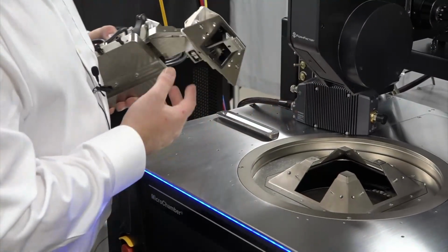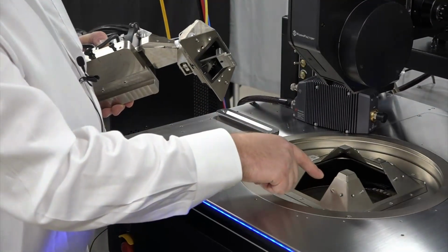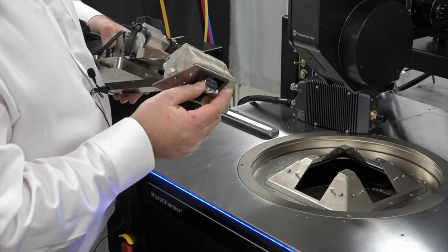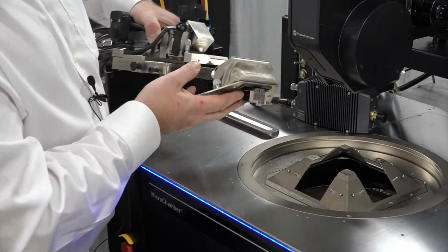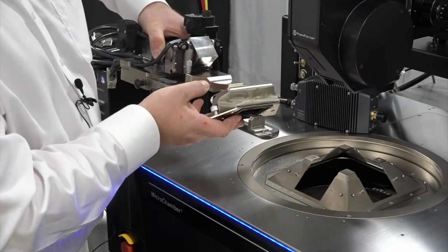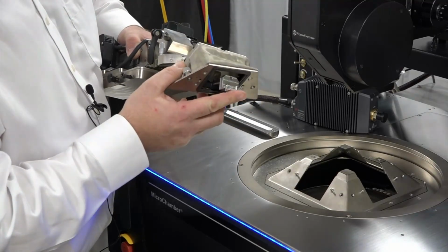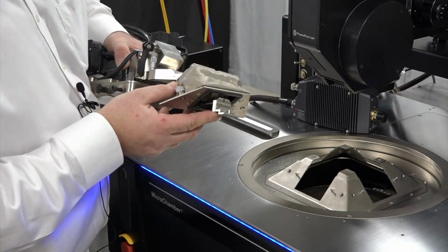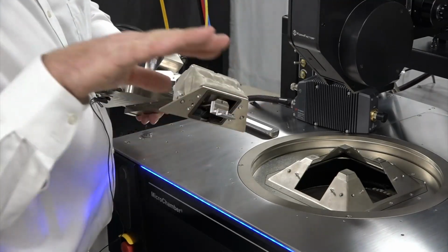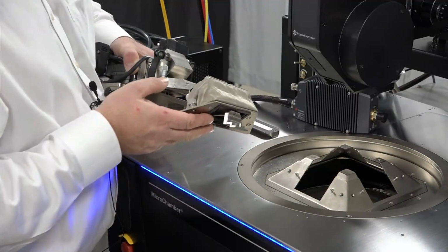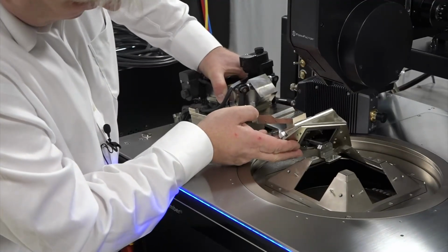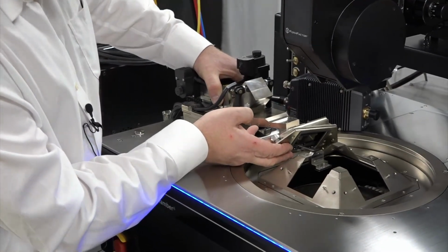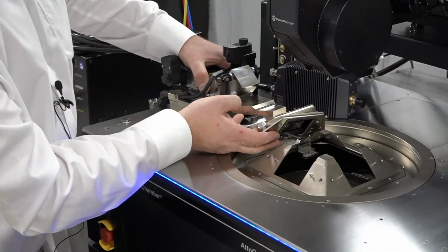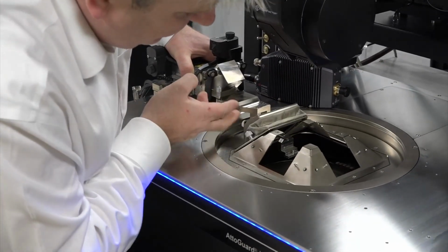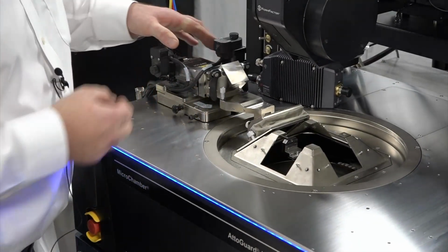So the other thing to note here is I've got my chuck in the low position. So there's no probe on there, but I don't want any chance, if I accidentally move it, of it grounding the underside of here on my chuck and potentially scratching it. So I drop the chuck so it's nice and far away from contact. I just push it so I can feel it engaging with the rail. I can watch it, make sure everything's clear, and it's good.